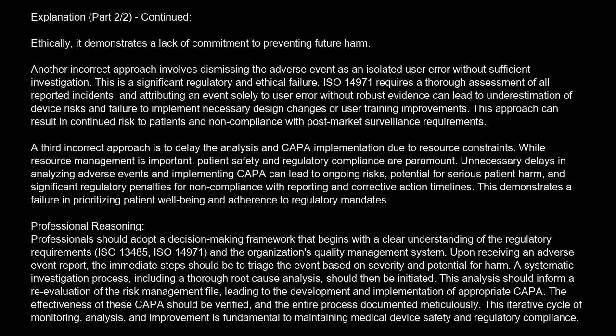Another incorrect approach involves dismissing the adverse event as an isolated user error without sufficient investigation. This is a significant regulatory and ethical failure. ISO 14971 requires a thorough assessment of all reported incidents, and attributing an event solely to user error without robust evidence can lead to underestimation of device risks and failure to implement necessary design changes or user training improvements. This approach can result in continued risk to patients and noncompliance with post-market surveillance requirements.